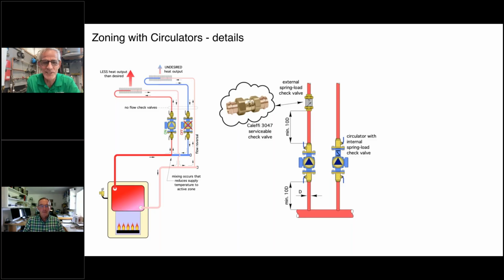And it's not a great place to have a check, right at the turbulent condition at the discharge of that circulator. So I would suggest a check like we show, separate and at a distance away from the discharge of the circulator. Just keep the rattling away.